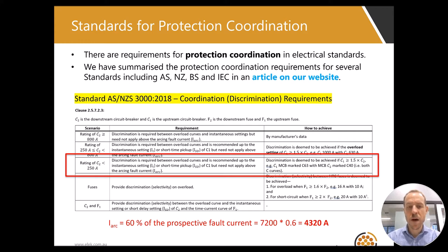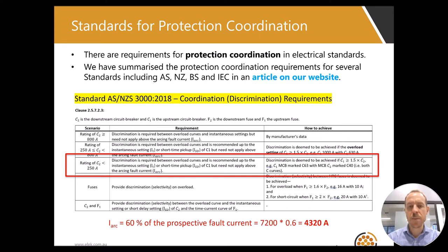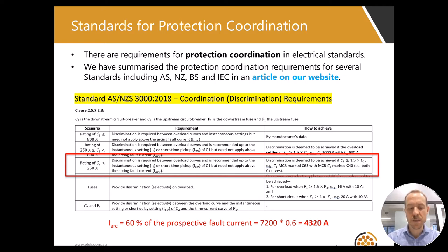For our example, the rating of the downstream breaker C2 will be less than 250 amps. From the table, the requirements are as follows: discrimination is required between overload curves and is recommended up to the instantaneous setting or short-time pickup of C1, but need not apply above the arcing fault current.